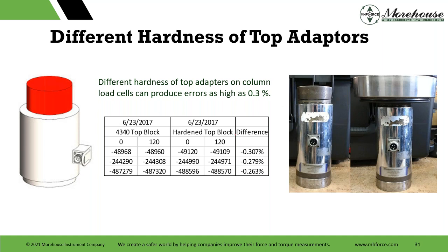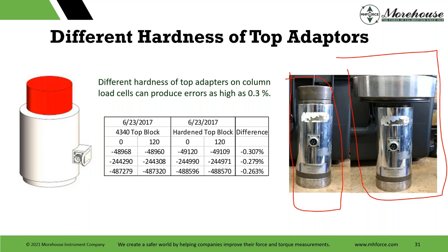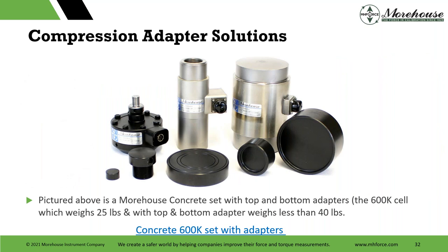These were different tests they did, and you can see on the side, they calibrated this load cell with the same bottom block both times, just changing the top blocks. Something as simple as that resulted in a difference of 0.307 at the 10% point and 0.263% at capacity, and it's so easy to correct just by using the adapters.